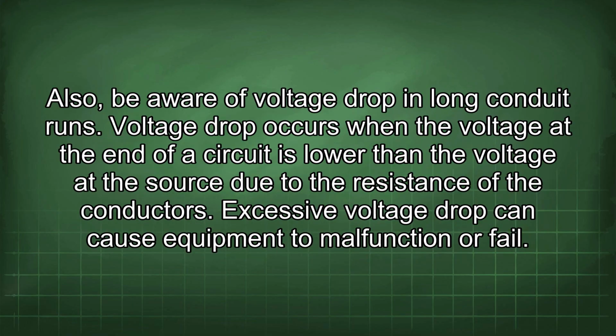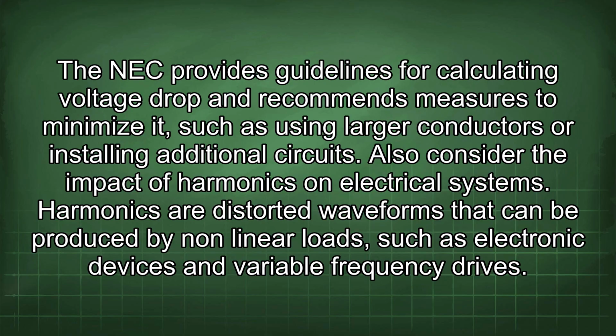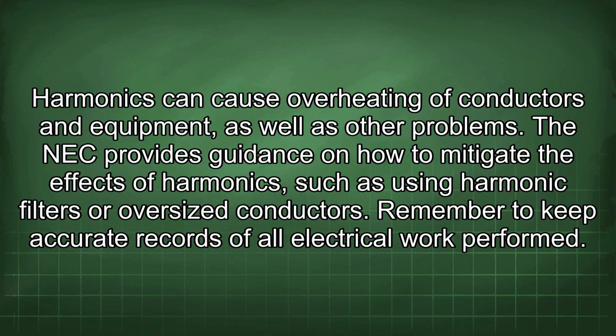Also, be aware of voltage drop in long conduit runs. Voltage drop occurs when the voltage at the end of a circuit is lower than the voltage at the source due to the resistance of the conductors. Excessive voltage drop can cause equipment to malfunction or fail. The NEC provides guidelines for calculating voltage drop and recommends measures to minimize it, such as using larger conductors or installing additional circuits. Also consider the impact of harmonics on electrical systems. Harmonics are distorted waveforms that can be produced by nonlinear loads such as electronic devices and variable frequency drives. Harmonics can cause overheating of conductors and equipment, as well as other problems. The NEC provides guidance on how to mitigate the effects of harmonics, such as using harmonic filters or oversized conductors.